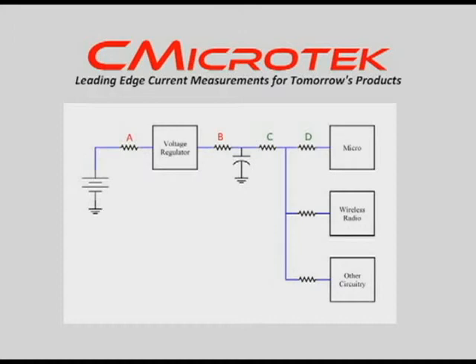First, the battery voltage will vary from its state of charge, output load, temperature, age, and other factors. With a device doing the exact same thing, the current measurements you take with one battery can vary considerably compared to another battery, or even with the same battery at different levels of discharge. For the device used in the demo, the battery voltage will drop from 4.2 volts when fully charged to just above 3 volts at the cutoff. And the peaks in the last waveform we looked at will range from 17 to 26 milliamps depending on the voltage level.